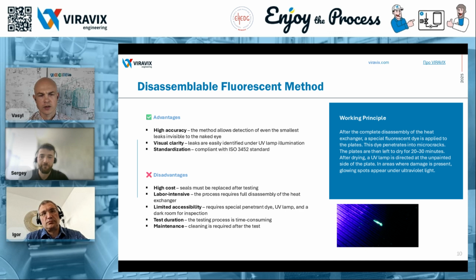Got it, thank you. Ihor, could you please tell me, from your experience, I've heard that some companies choose the fluorescent method as their only testing method. So, when they need to check equipment for leaks, they do it during a scheduled production shutdown, fully disassemble the heat exchangers, replace the gaskets if necessary, and then perform fluorescent testing across the entire heat exchanger. And have you come across similar approaches? That would be my first question. And second, based on your experience, what do you see as the main advantage of the fluorescent method? And if there are any additional drawbacks you've encountered in practice, we'd really appreciate it if you could share those as well.